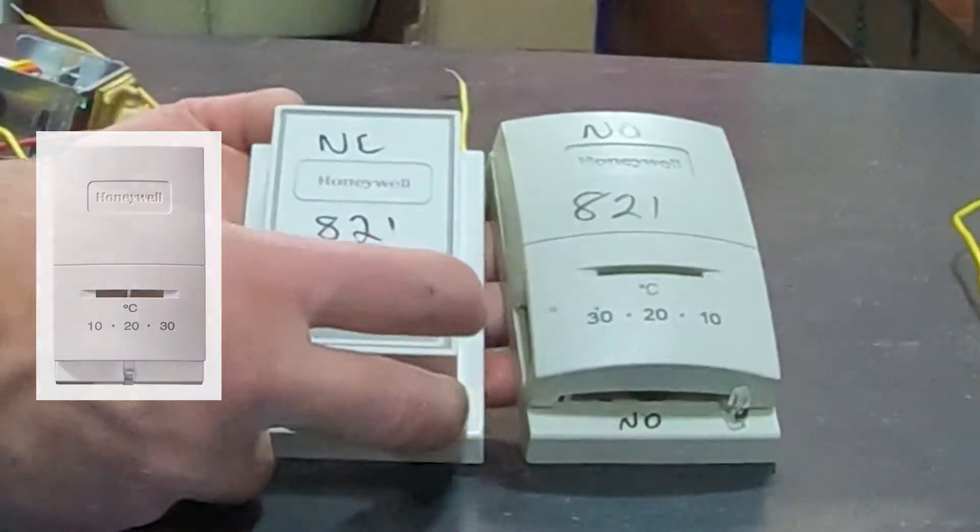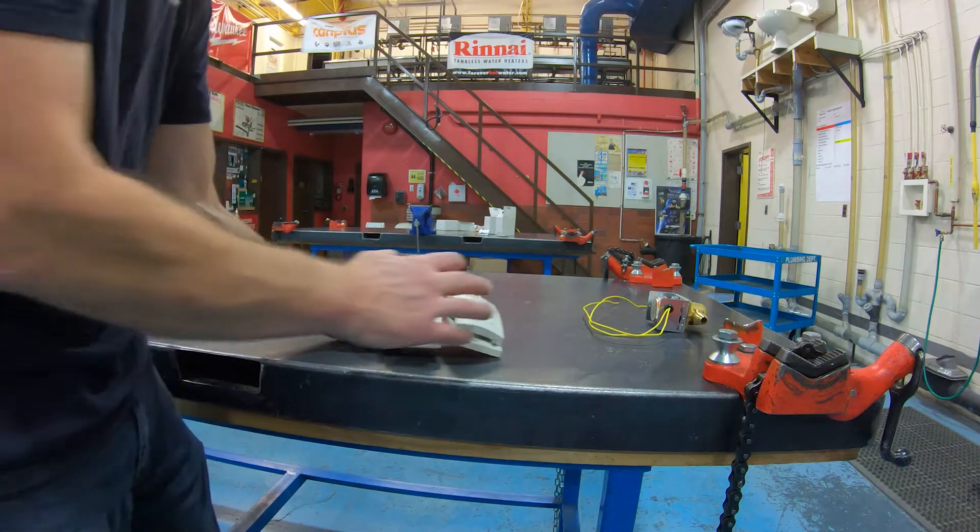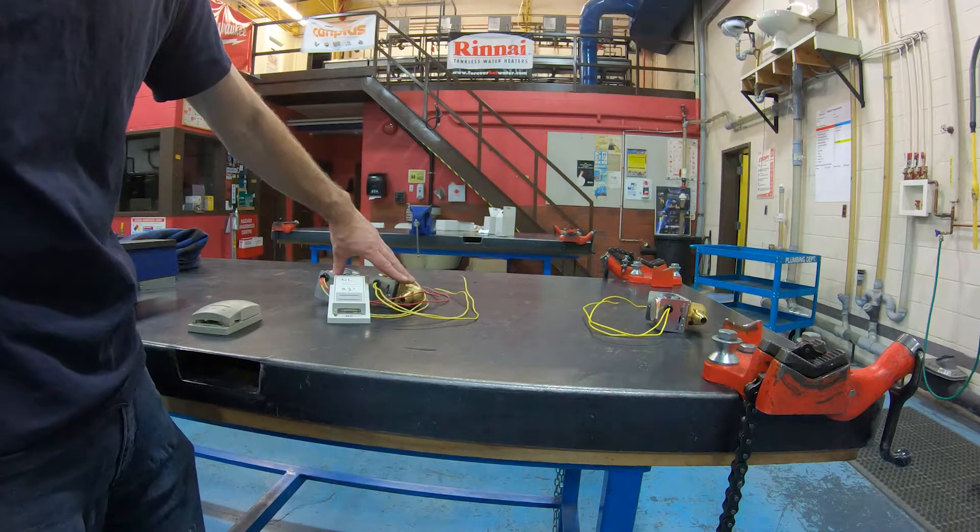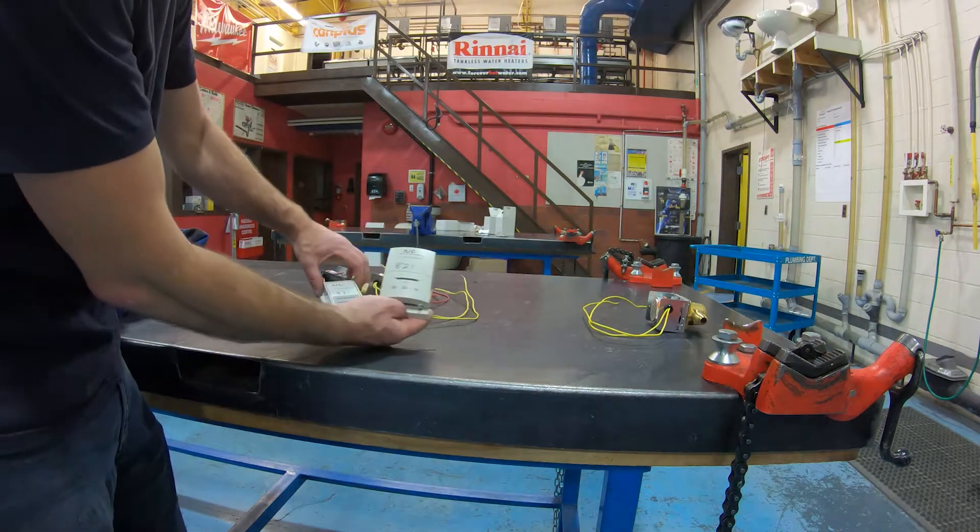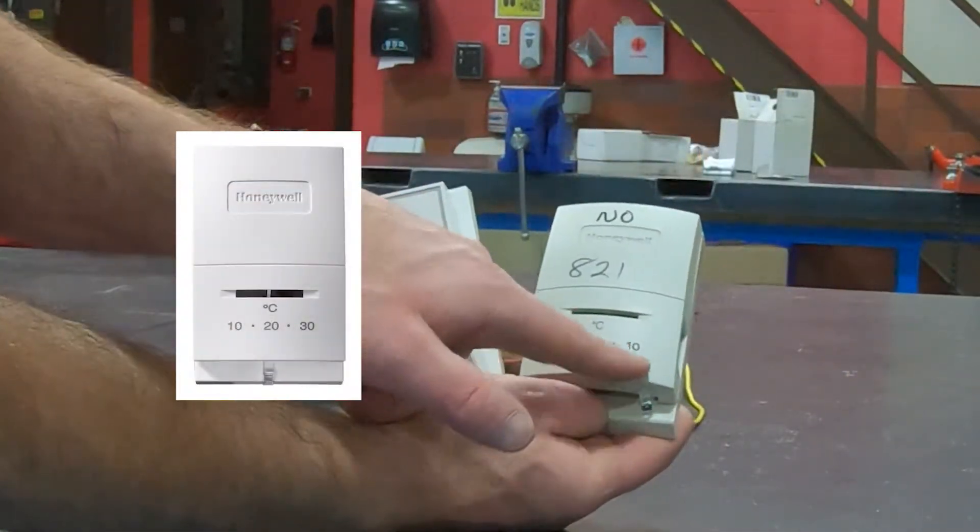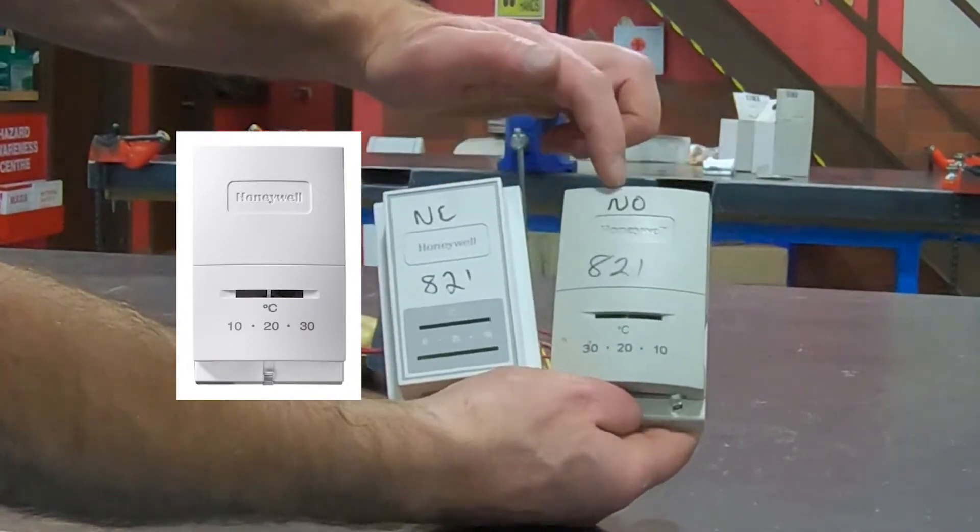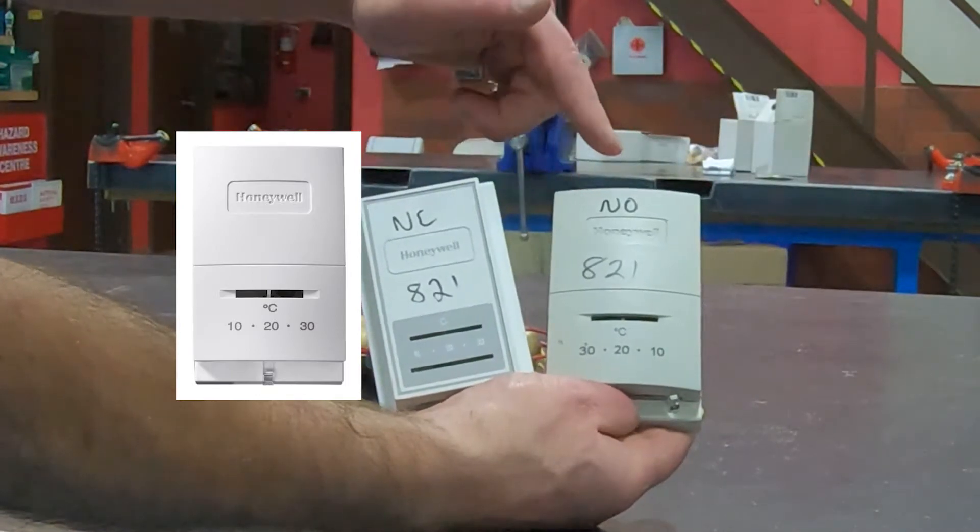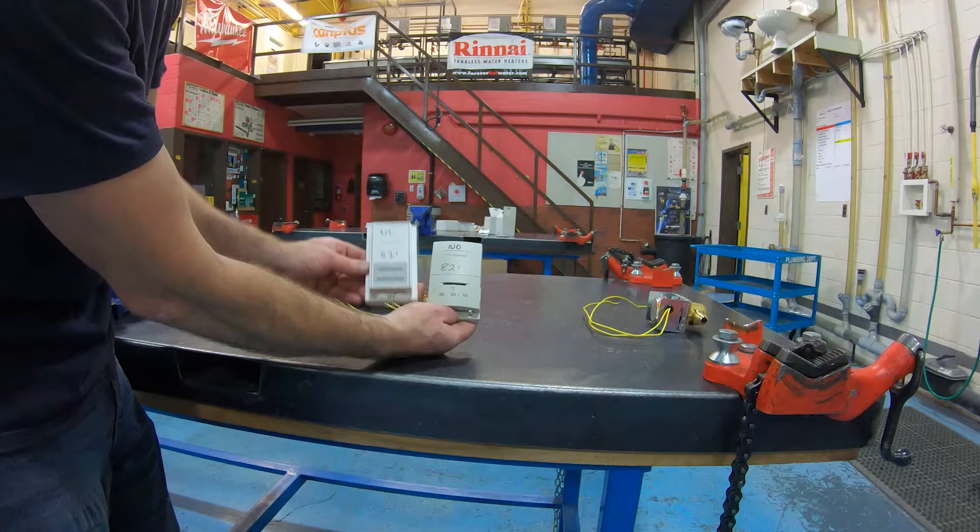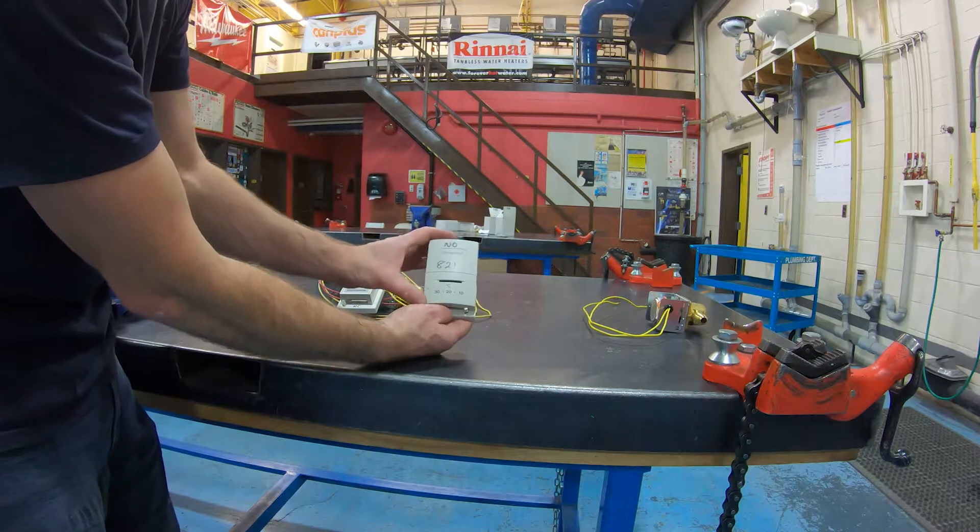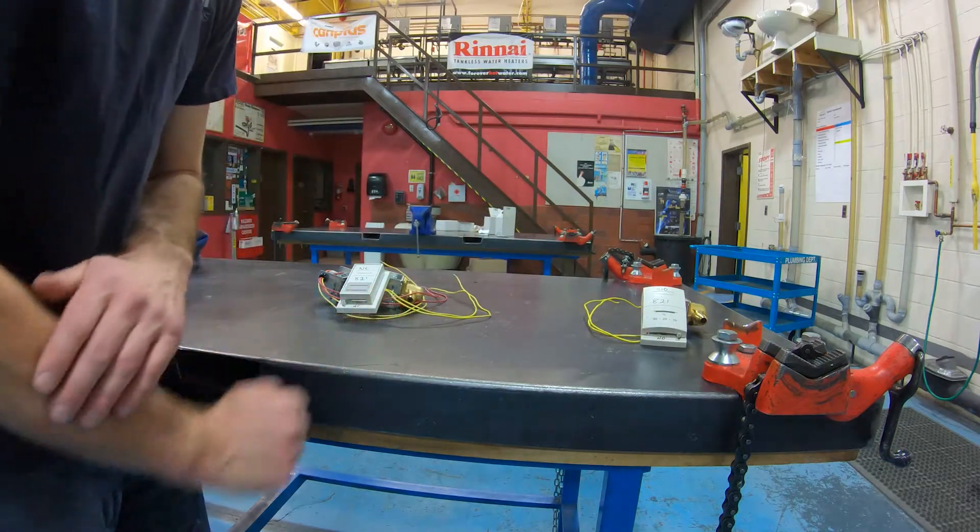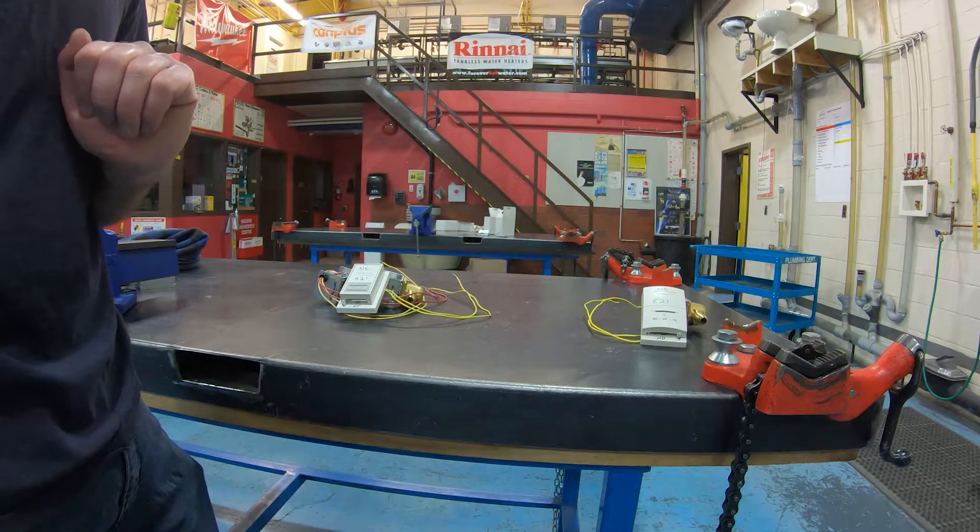Now the normally closed thermostat is for the two normally closed zone valves. This other one here, you may have noticed, has the numbers in reverse, 30 to 10, 30 to 10. This is a normally open thermostat. This thermostat operates in reverse of this one, so you don't want to mix the two up ever. Normally closed goes with the normally closed zone valves. Normally open thermostat goes with the normally open zone valve. If you mix them up, you're going to have a problem. It's going to act in reverse, so don't screw those up.